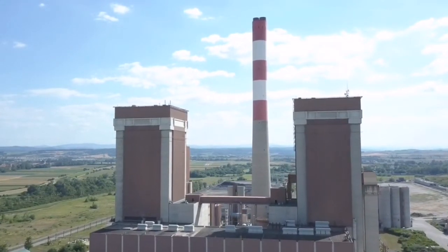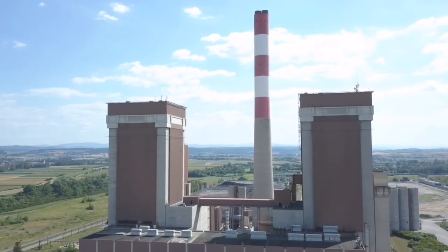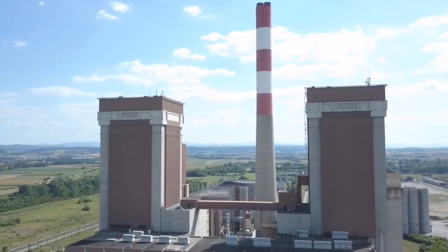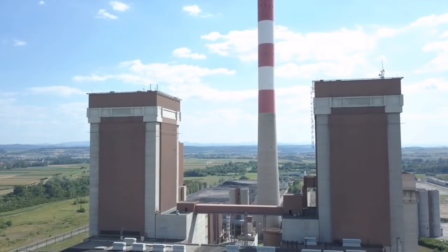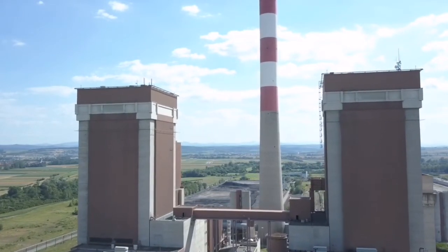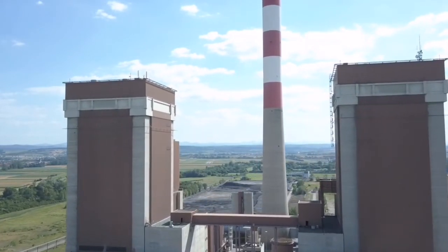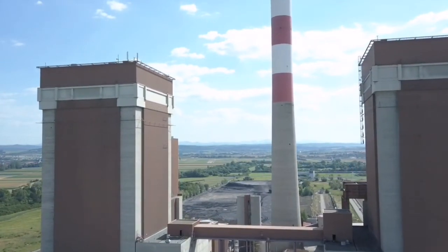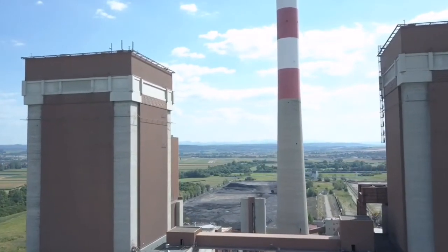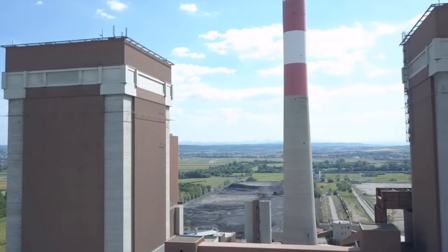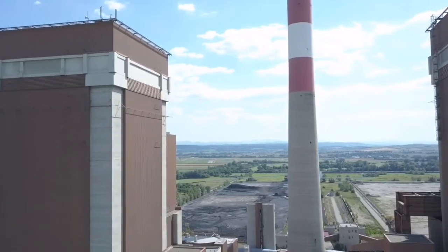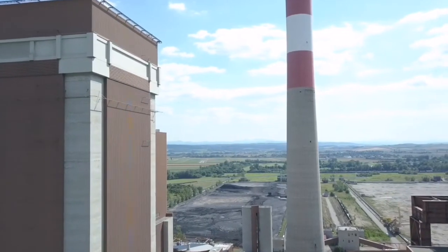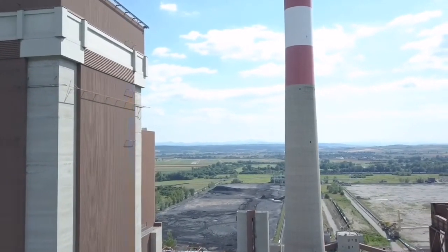The saturated steam from the steam drum or once-through system is sent to the superheater to produce dry steam, which is required for a steam turbine. Preheaters are located at the coolest end of the heat recovery steam generator gas path and absorb energy to preheat heat exchanger liquids such as water, thus extracting the most economical amount of heat from the exhaust gases.